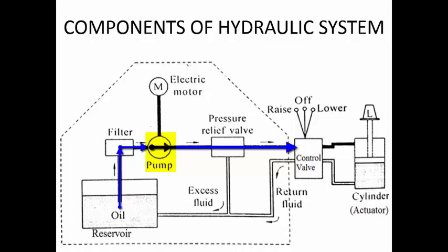So in order to limit the system pressure, we have something called a relief valve. The relief valve works in the same way as the dead weight on a pressure cooker. In a pressure cooker, as you are boiling water, the water will be converted into steam, and as you continuously supply heat, more and more steam is generated and the pressure inside continuously rises. When the pressure rises beyond a particular value, the pressure will have sufficient energy to lift the weight placed on the cooker, and the excess steam which is increasing the pressure will simply escape into the atmosphere.